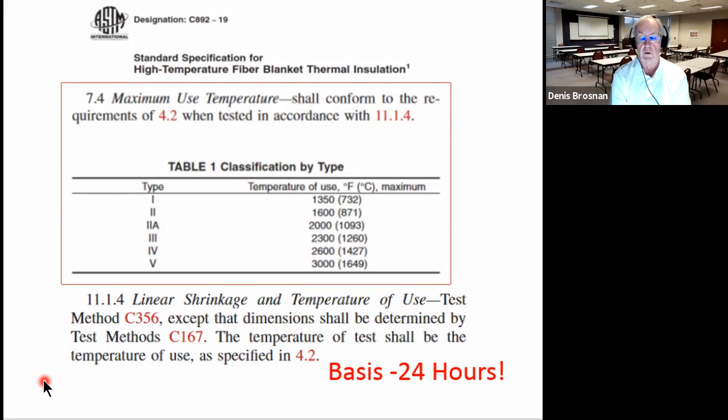Well, that's where it's hotter, right? So I went up there and I walked down through the kiln with a spotlight and looked up at the cracks, took some pictures and stuff, like I knew what I was doing. And then we walked out for the inevitable meeting in the plant manager's office, and he said, "We're going to sue those guys. You know, we put up a 2,000 degree rated insulating material in the crown."